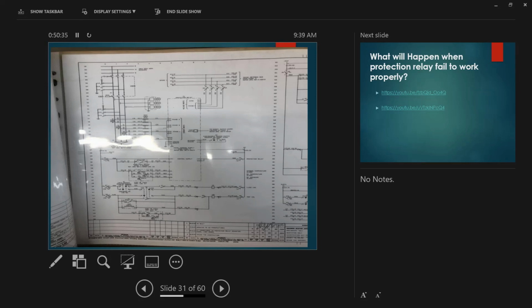Can you do that from the front, or do you need software? Software. That's why familiarization, plus knowing how to understand the PLC or logic inside the relay, is important. Because I have another example, I think that one was in the Northern Territory. What happened was they forgot to add an additional inhibit to test the relay. So when the breaker is racked in, there's a particular logic, they call it the virtual output.